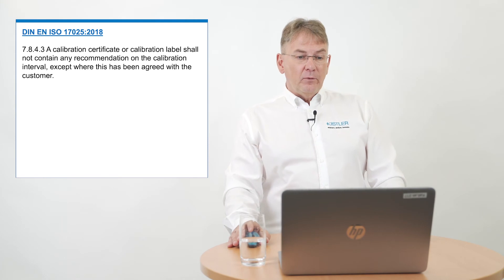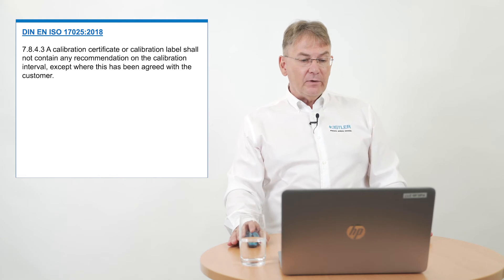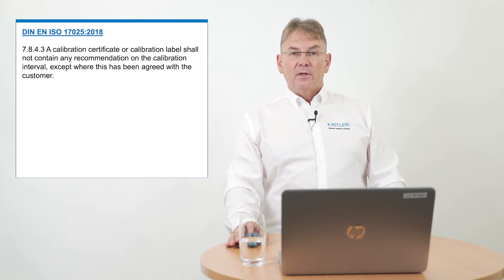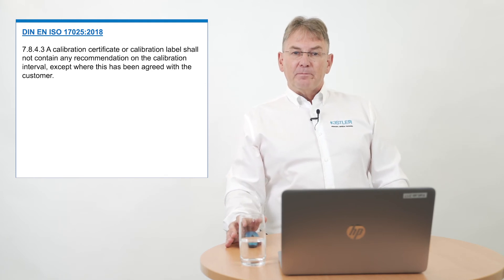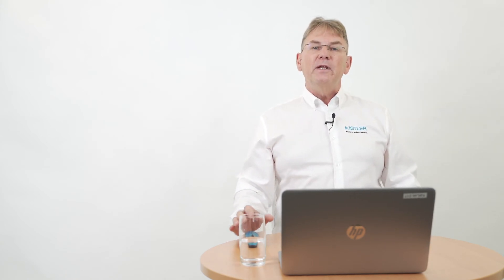Another point written in this norm is that a calibration certificate shall not contain any recommendation of the calibration interval. The interval is part of your — the customer's — quality management system. You are responsible for your interval, so no calibration laboratory can give you one. But the norm continues and says 'except where this has been agreed with the customer.' So if you tell the calibration laboratory to include an interval of 12, 24, or other months, that would be acceptable. The laboratory itself may not give you an interval on its own.